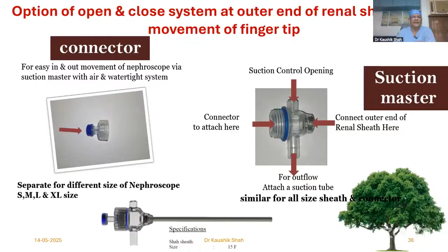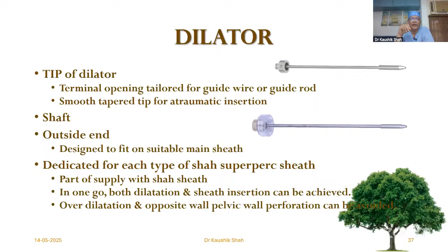The dilator has a tip which can accommodate a guide wire for 12, 15, and 18, and it can accommodate the guide rod for 21 and 24. So you can use any size, and it is dedicated for each sheath. It is a part of the Shah sheath supply, and therefore in one step you can both dilate and insert the sheath in one sitting. The possibility of over-dilatation and opposite wall pelvic perforation can also be limited.